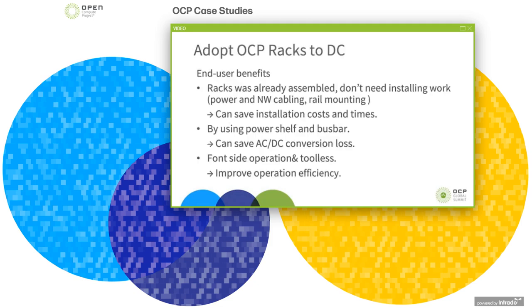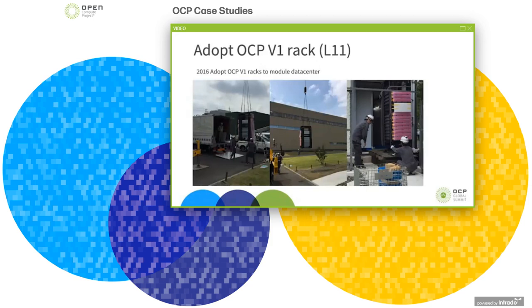Let me talk about adopting OCP racks in our data center. Unlike a standard 19-inch rack, OCP IT gear is pre-installed into the rack, which helps cut down the cost and time of installation. There is no power supply on an OCP server; every single rack only has 1 or 2 power shelves to convert AC to DC. As a result, it has a higher AC to DC conversion rate than a traditional rack. No tool is required for regular maintenance, which also saves precious engineer resources.